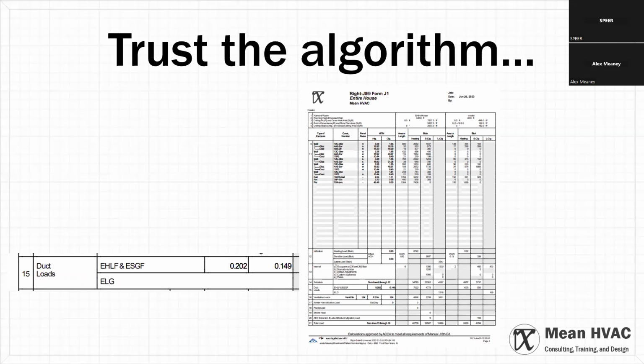You can change a window on a building and the duct load will change, because that window helped determine the rest of the load, which determined the size of the system, which determined the CFM, which determined the surface area, which gets fed into the load calculation for duct load. It's a snake eating its tail—it just keeps going around in circles, and it's pretty complicated.